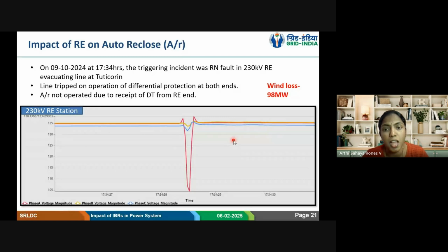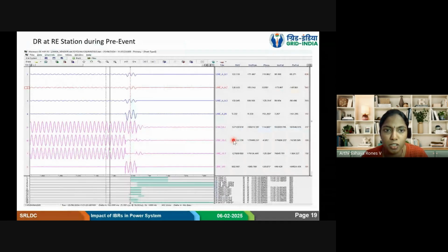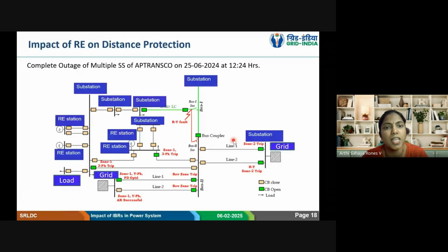Most of the REs connected at central level are having differential protection. So this homogeneity kind of issue, what I discussed previously, can be avoided to some extent, or to a greater extent we can tell, in differential protection. Differential also, if the angular variation between the grid end and IBR end is very high, then differential also can maloperate. Literature is telling.